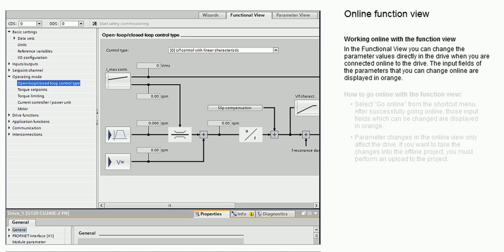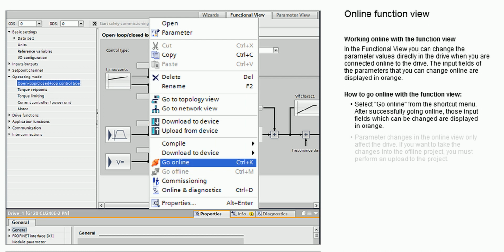Working online with the function view. In the function view, you can change the parameter values directly in the drive when you are connected online to the drive. The input fields of the parameters that you can change online are displayed in orange. How to go online with the function view. Select Go Online from the shortcut menu. After successfully going online, those input fields which can be changed are displayed in orange.